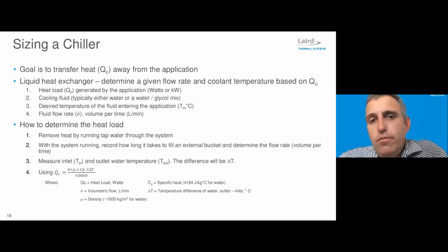And then we can measure the temperature of the liquid going into the system, and the temperature coming out of the system while it's being used at full heat removal capacity. With that, we get our set point, which is the inlet temperature. Then we take the temperature rise, knowing our mass flow through the system and what type of fluid it is, and we can use a pretty simple calculation to determine the heat load. Albeit this is a little bit crude and simple, it gives us a good starting point, and with some margin on top of these calculations, we can size a product that can meet our cooling needs.